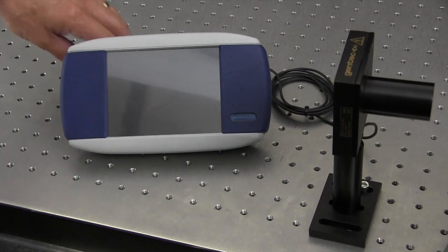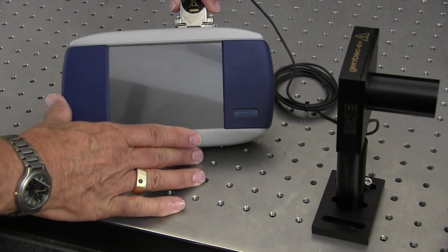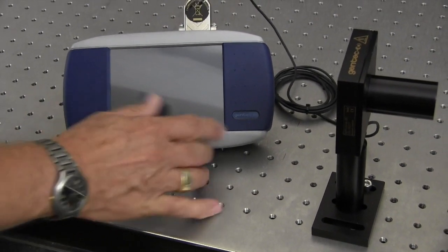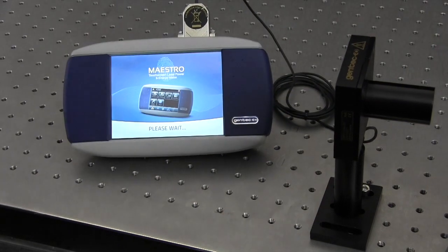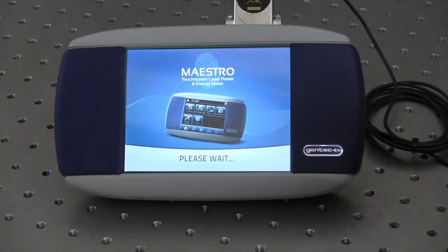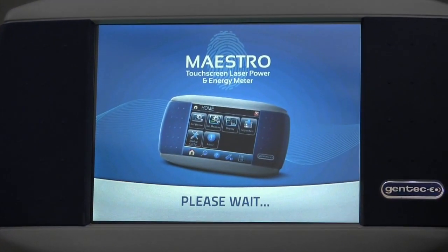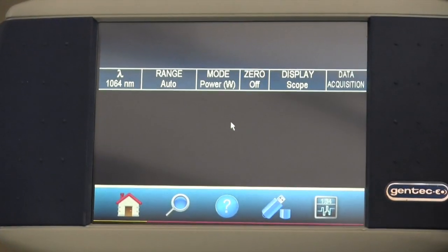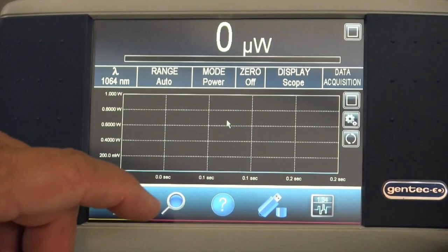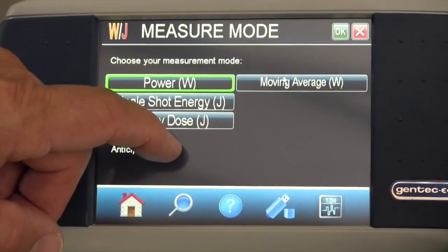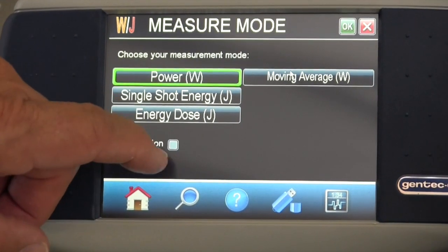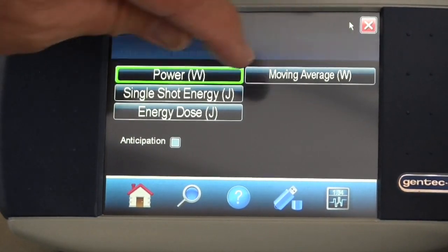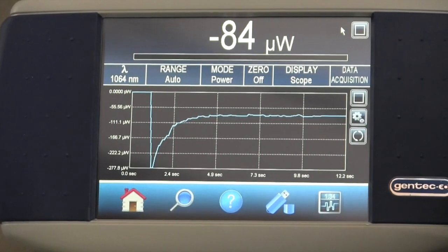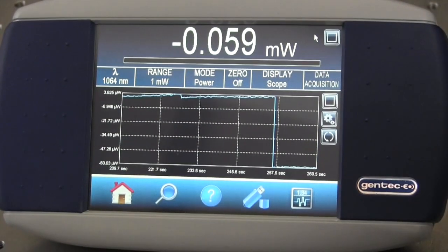Now let's plug the XLP12 probe into the Maestro and turn it on. Next, we want to turn off anticipation or speed up. This will give the probe a slower response to the fluctuations in the laser power and enhance the stability of our measurement.